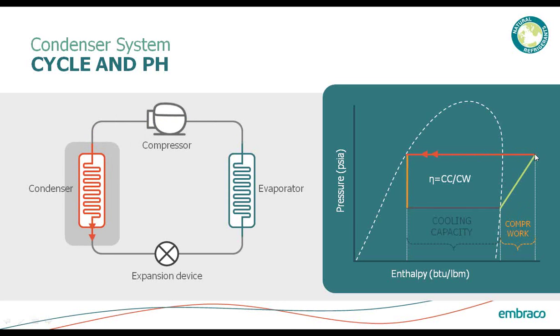At which point we enter the condenser. That condenser is going to de-superheat the vapor — we're going to get rid of sensible heat until we hit the saturated vapor line. Once we hit that saturated vapor line, it just starts seeing a change in state, so you would not notice much temperature change until you hit the saturated liquid line. If you continue on past there, you continue to subcool the liquid, and we'll talk about why that's important.